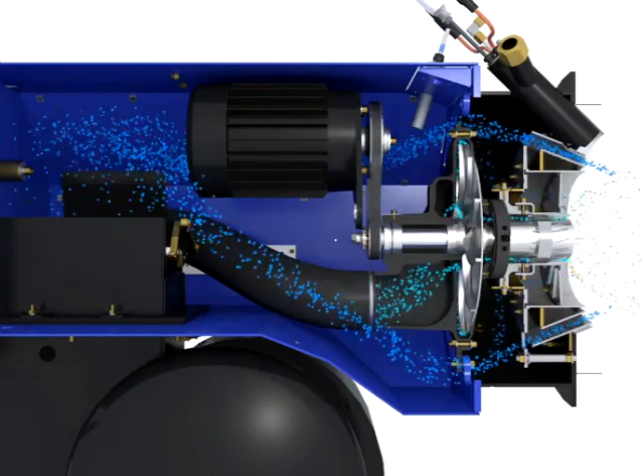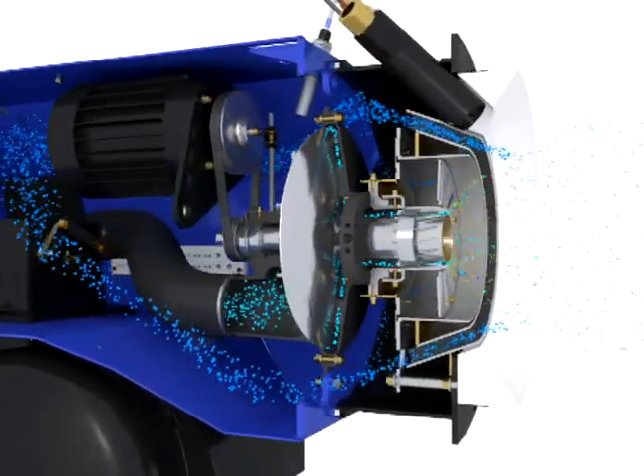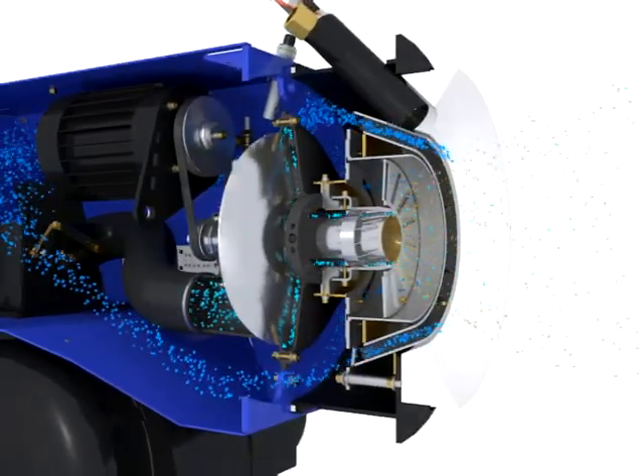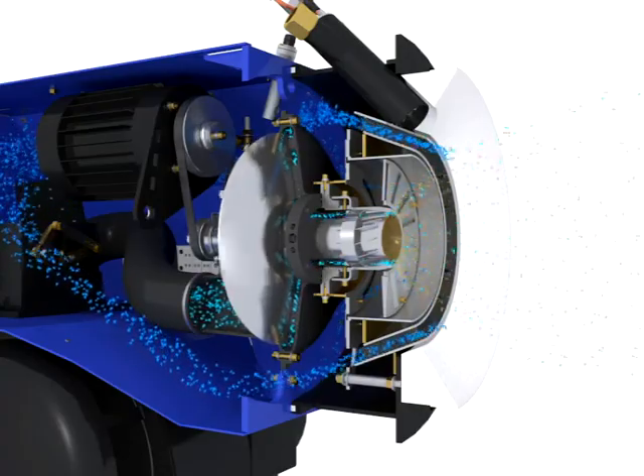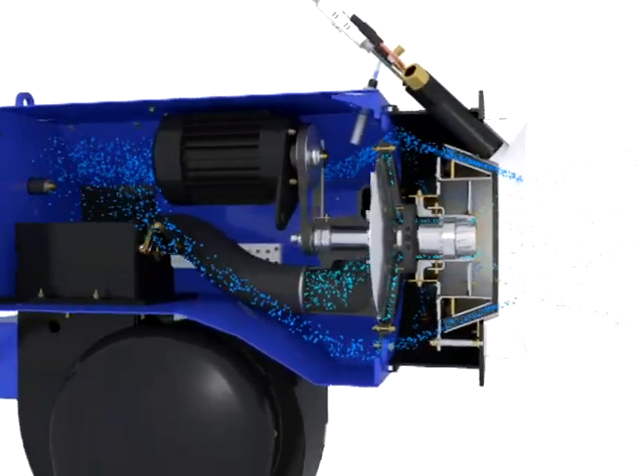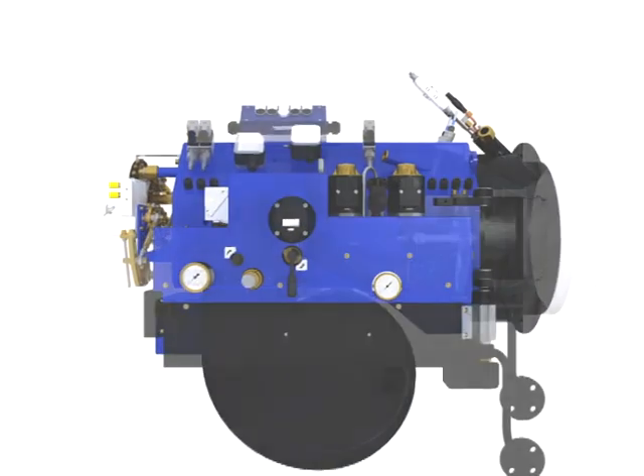At the same time, these droplets are deflected to the best atomization angle. The secondary air, shown here in light blue, supplies the largest portion of the oxygen that is necessary for combustion and determines the shape of the flame when it is formed.